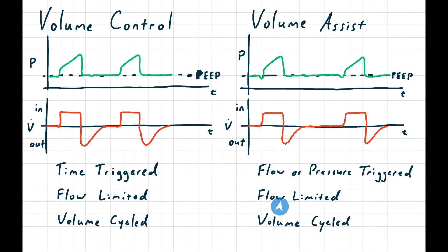The limit and cycle are exactly the same in assist mode compared to control mode. The patient decides when to start the breath, but they don't decide when to end the breath. We're still flow limited, so the patient doesn't decide how much of a breath to take. We're still volume cycled, so the end of inspiration still comes after the programmed tidal volume is met. In a pure volume assist mode, if the patient decides not to breathe for a couple of minutes, the ventilator won't do anything — it just won't give any breaths.